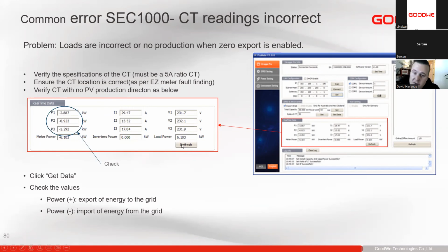So it's always good to do this when there is no PV production. The AC can be on, the PV can be onto the inverter, but we leave the inverter's AC power off. The reason for that is so that we're not consuming or producing any PV power to alter the readings that we're seeing here. So you press refresh and then it will give you a snapshot of the data that we're seeing. So all these values need to be negative. So negative means consumption from utility. So we need to check and verify that all these values are negative.